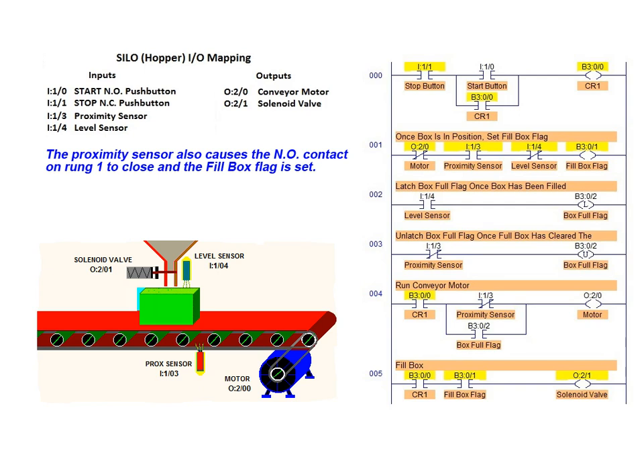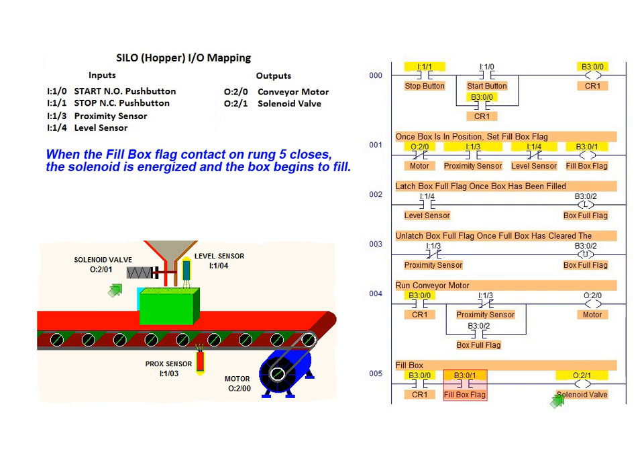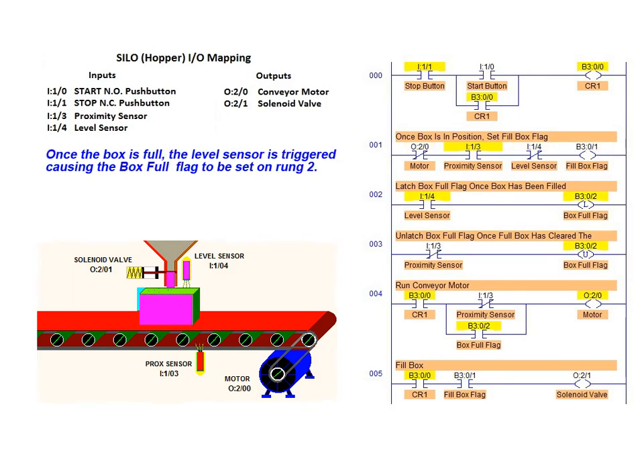The proximity sensor also causes the NO contact on rung 1 to close, which in turn sets the fill box flag. When the fill box flag contact on rung 5 closes, the solenoid valve is energized, and as a result, the box begins to fill. Once the box is full, the level sensor is triggered, causing the box full flag to be set on rung 2.